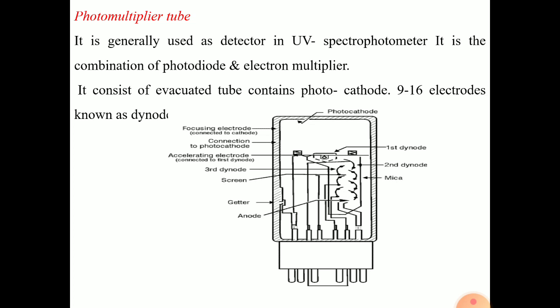And a photocathode will be there. When radiation falls on the photocathode, electrons will be produced. The produced electrons strike the dynodes. First one electron will come and strike the first dynode. That dynode is coated with an electron emissive layer also, like the phototube. At the dynode's inner surface, one electron undergoes multiplication. So one electron is converted to a second electron.